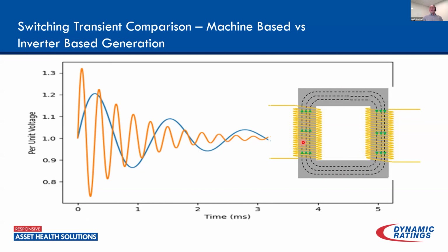Of course, when we look at the windings in a transformer, what we're looking at here is an inductor. So what happens when I hit it with that high frequency transient? Inductors, of course, resist instantaneous changes. And because of that, the stress of that switching transient is going to be pretty much localized to the first few turns in the transformer. So that's why, when they look at failures on renewable applications, typically it's going to be the first few turns of the winding that experience that problem. Because when they have those switching transients, all of that stress is going to be isolated to those first few turns.